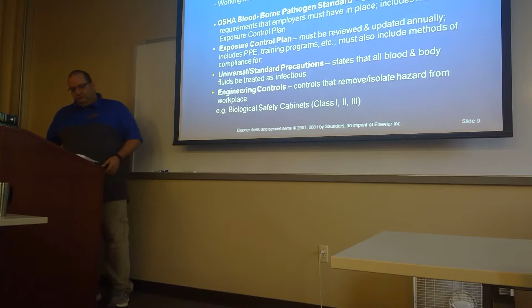There are three classes of biosafety cabinets. Class 1 does nothing but maintain negative pressure, making sure airflow comes away from you, not toward you. Class 2 is what you see in hospitals and what we have here. The airflow goes down, gets filtered, goes up, gets filtered again, and is exhausted back out. It has multiple layers, two to three, of HEPA filters to make sure nothing gets back into micro or into the outside air.